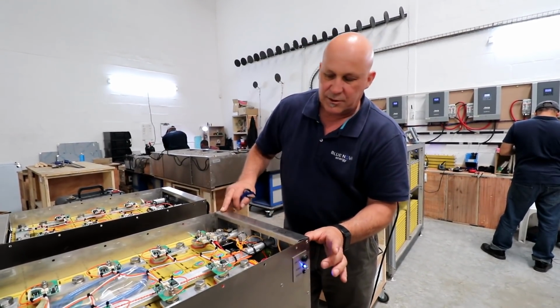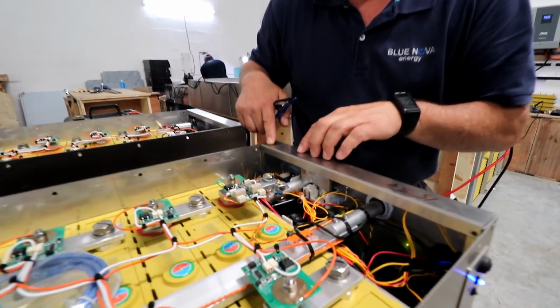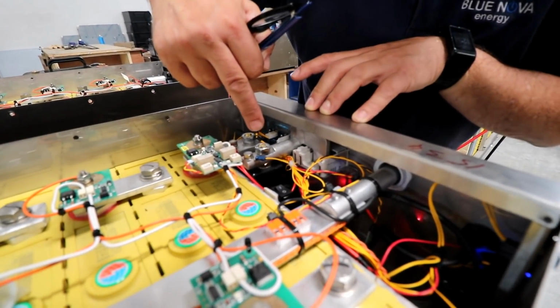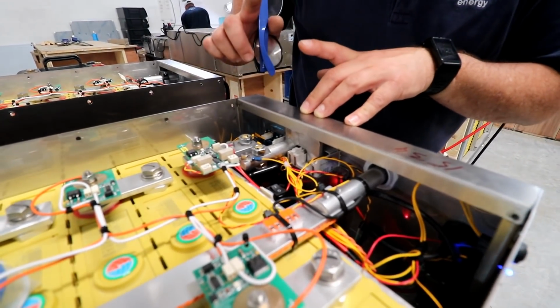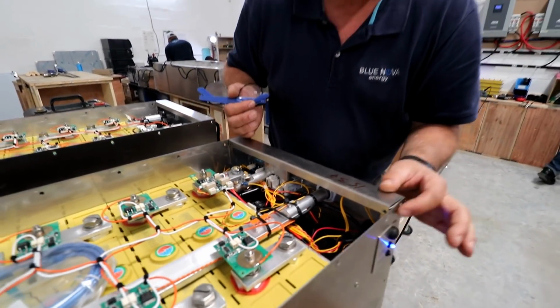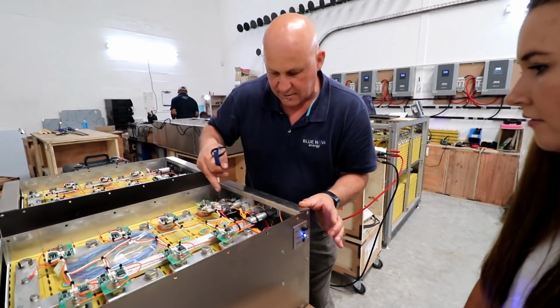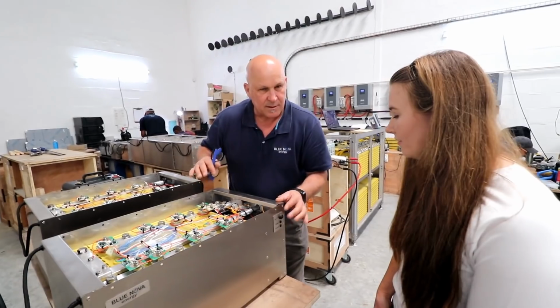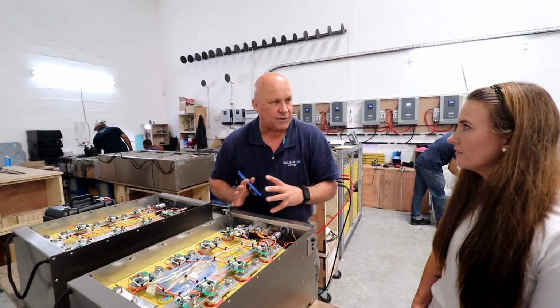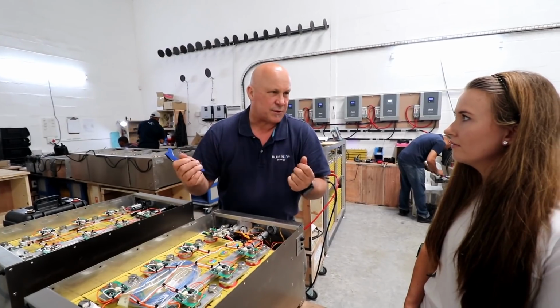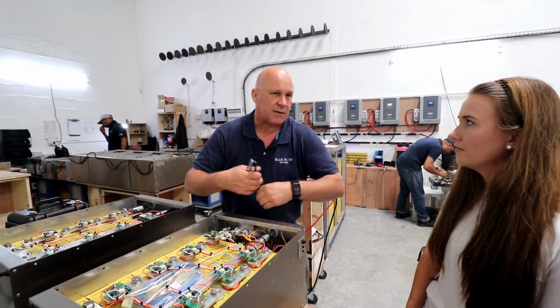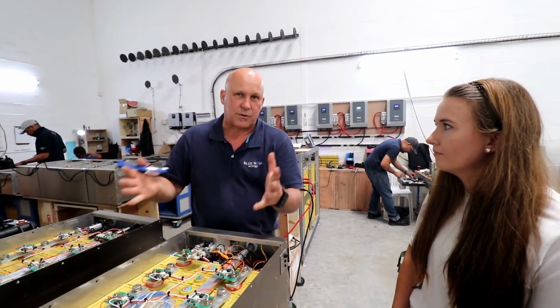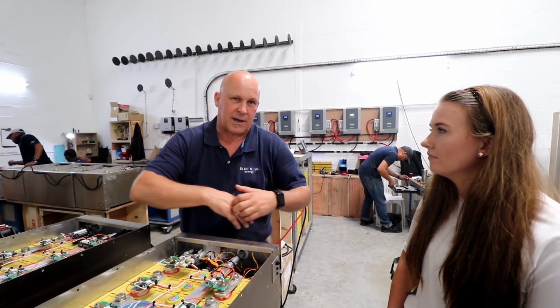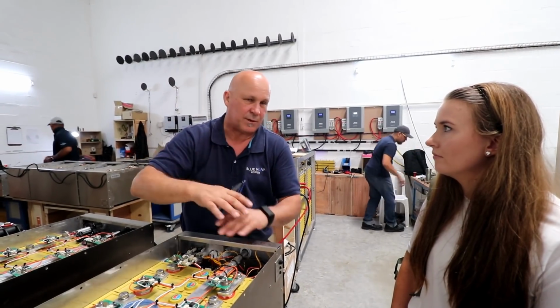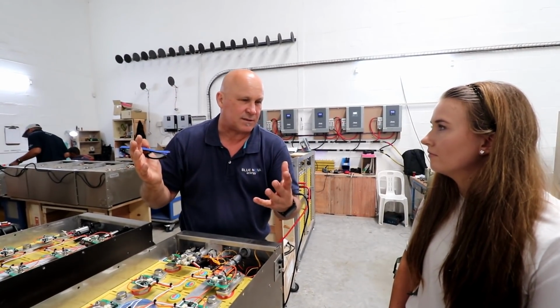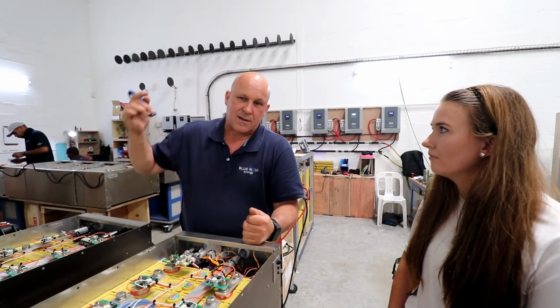We switch the battery on. You can listen here closely. It'll charge that voltage up. And then there's this high power impulse relay, which we then close if the conditions are fine. And if there's a fault, then it will trigger that and you can then hear the breaker opening up. And that is a very unique feature in the Blue Nova batteries. If we have a fault, like a high temperature, and the fault clears, then we will automatically reclose that. So if you park your yacht in Dubai and everything is closed and the sun's shining through the battery room and the temperature goes above, I think 65 degrees Celsius, we'll open the contactor, everything will shut down.